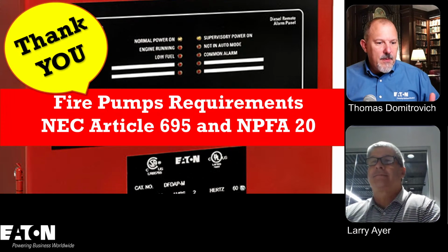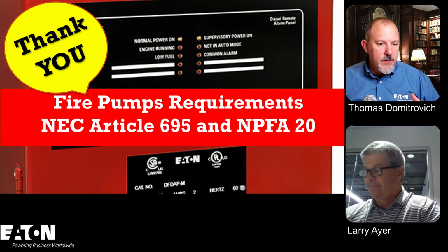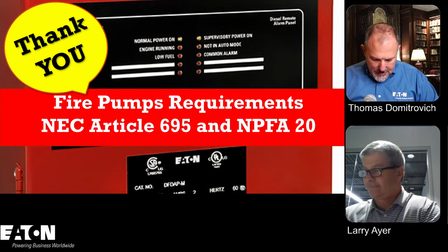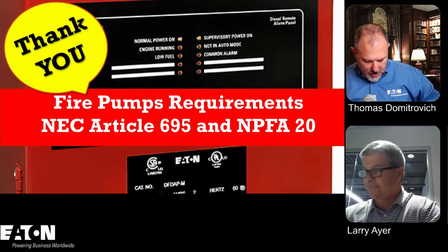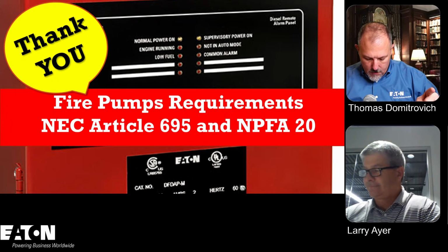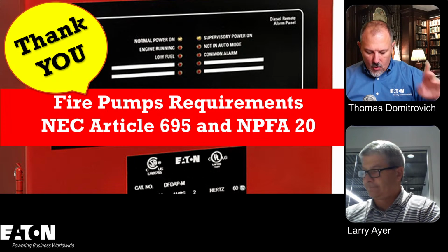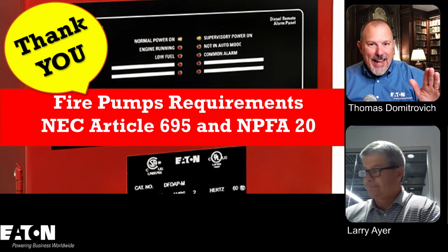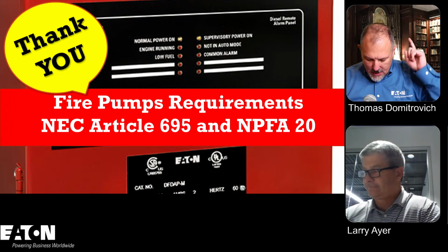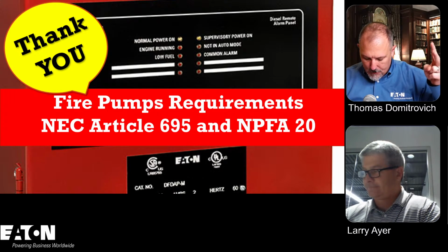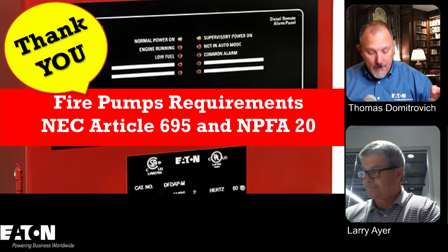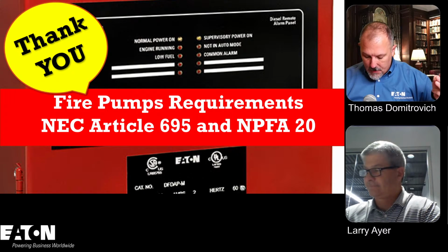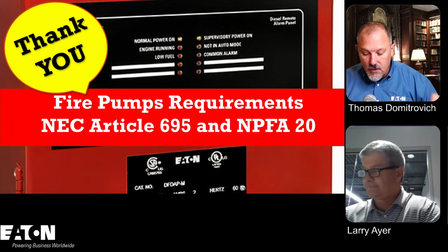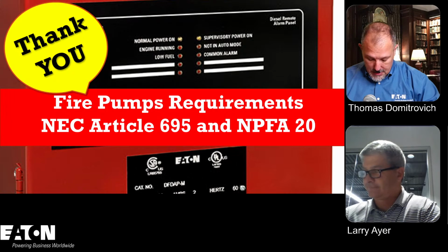Everybody, thanks for joining in. What is the section? The section for that listed transfer switch is 695.4(B), connection through disconnecting means: (1) number of disconnects, (A) general, and then (2) a listed fire pump power transfer switch, and (3) a listed combination fire pump controller and power transfer switch. It's buried in there. It could be more clear, but it is in there.